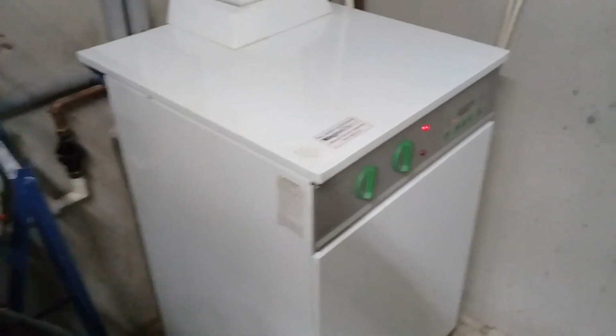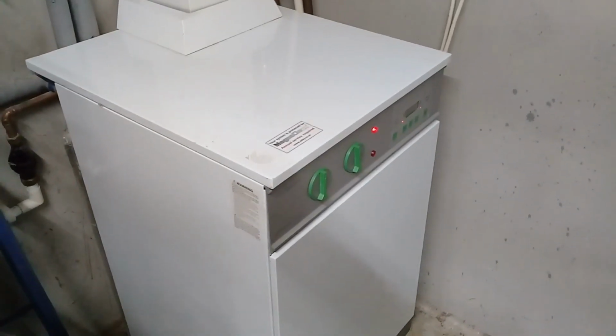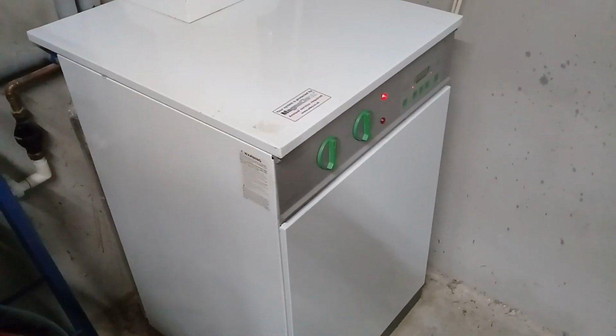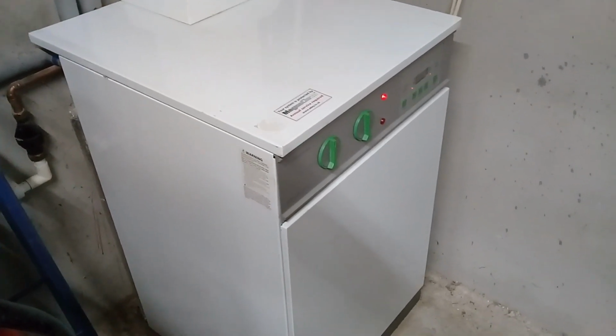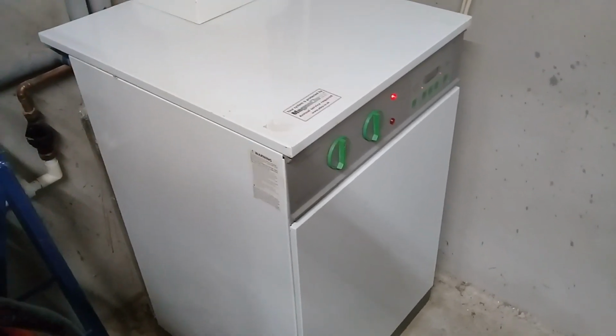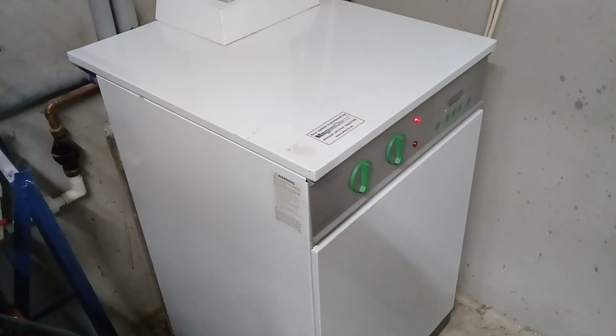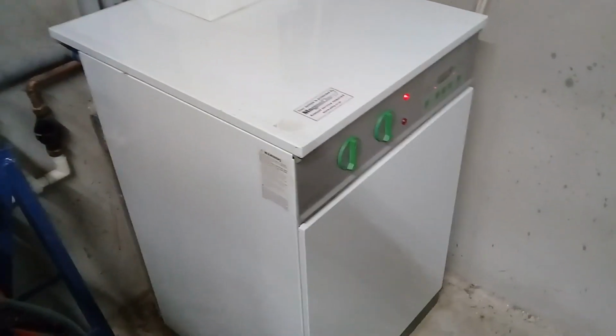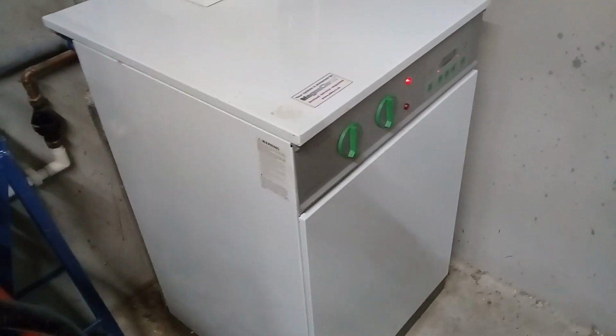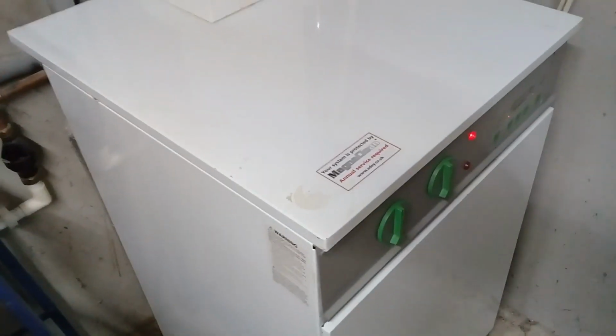So something wasn't right. It can be a few things: circulation, the pump, the diverter valve, blockages. So there's a few things to look at. So let's have a look at the boiler, and I'll give you some indication as to what went wrong with this one anyway. Right, so covers off. Let's have a look, see what we've got.